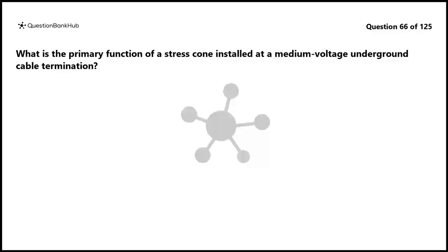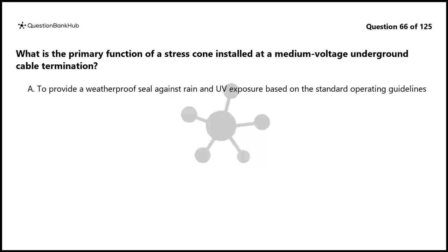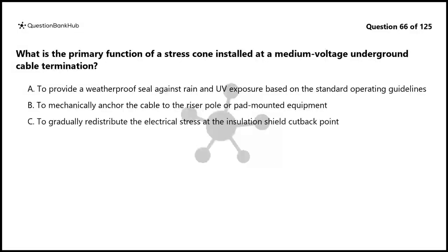Question 66. What is the primary function of a stress cone installed at a medium voltage underground cable termination? A. To provide a weatherproof seal against rain and UV exposure based on the standard operating guidelines. B. To mechanically anchor the cable to the riser pole or pad-mounted equipment. C. To gradually redistribute the electrical stress at the insulation shield cutback point. D. To increase the current carrying capacity of the cable at the terminal end.